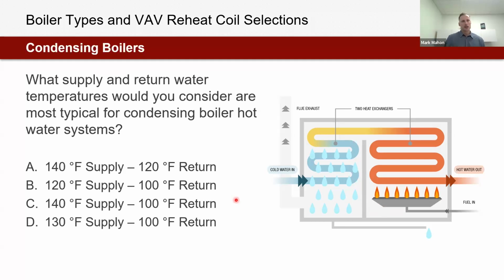So moving to condensing boilers, once again, right into the Q&A panel here. My same question, but in the context of condensing boilers, what is most typical for a condensing boiler system? We have A, 140 to 120, B, 120 to 100, C, 140 to 100, D, 130 to 100. I'm seeing some A's or B's. Randy's saying A, Armando saying A or B, Nick saying A. So some good answers there. I'm seeing a C, which is from Jonathan. And so I will say, more variety in the responses here.